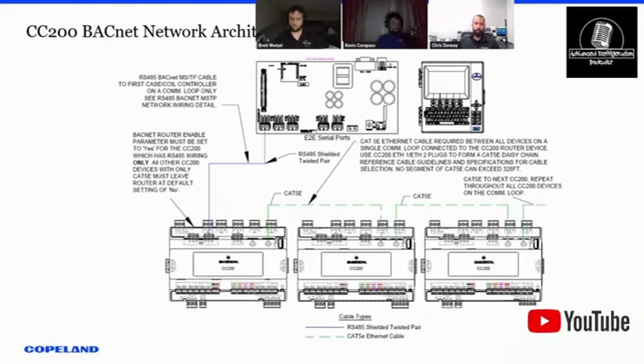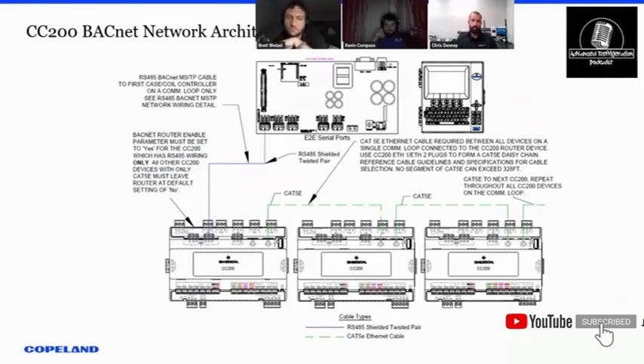This has a big fringe benefit in that customers that group defrost together into lineups or circuits or defrost groups, whatever lingo you want to use, but customers that use lineups, we're able to do all the defrosting and all the case-to-case communication through this Cat5 cable. The lead case goes out and contacts all of the slave cases and coordinates everything. It's incredibly reliable. It's super fast. It allows us to grab and synchronize a ton more information than we have ever been able to with RS-485.